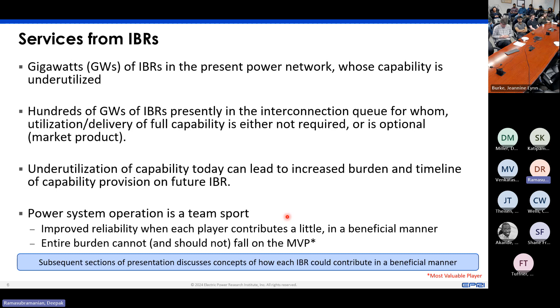The services we spoke about previously, which we'll require more and more of, can be categorized into five categories: fast and stable response, maintaining voltage, maintaining frequency, robust fault ride-through, and black start capability. We do need the ability to black start the grid in case of a blackout.